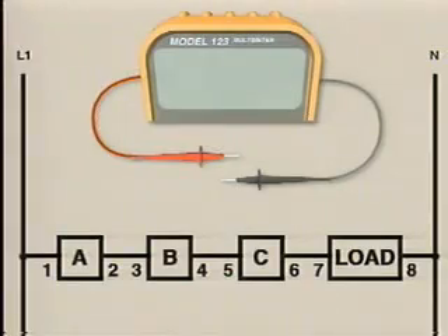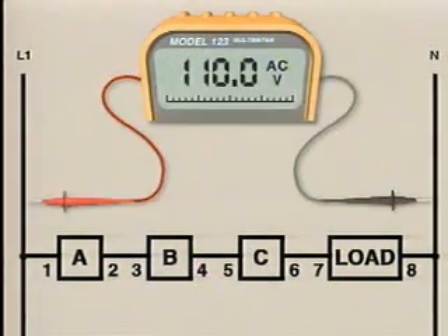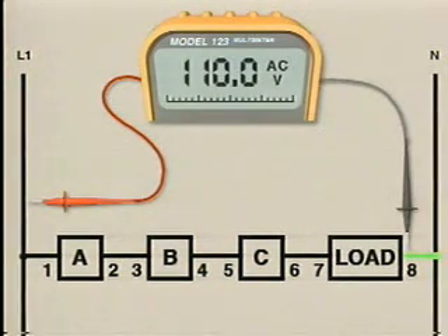We can use the same illustration that we looked at earlier to show how the half-splitting method can be used to troubleshoot a problem. As we did with the serial method, we'll assume that a problem exists in this circuit and that we know the circuit has the proper operating voltage. We'll also assume that the wire connecting test point 8 to neutral has been tested and found to be good. By eliminating this wire as a possible cause of the problem, we can use test point 8 as the reference point for our voltage measurements.